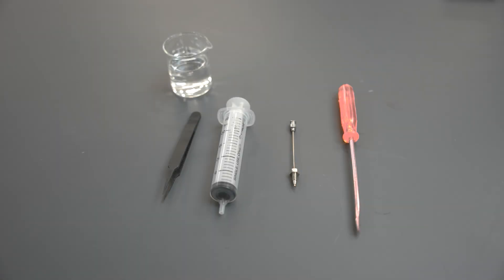For this procedure, you will need a flathead screwdriver, plastic tweezers, a syringe that has a needle with a nut and ferrule, 2-propanol, and replacement lenses and gaskets.